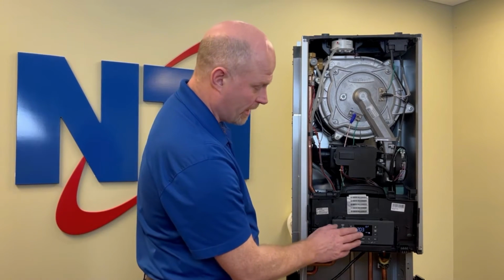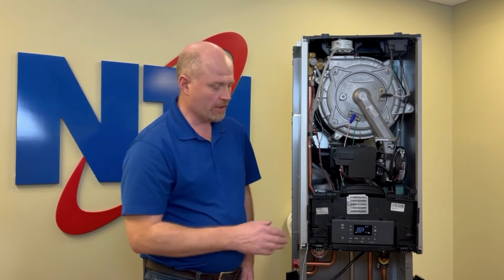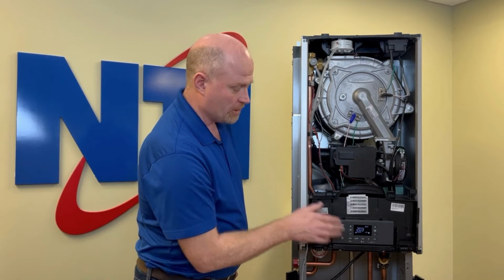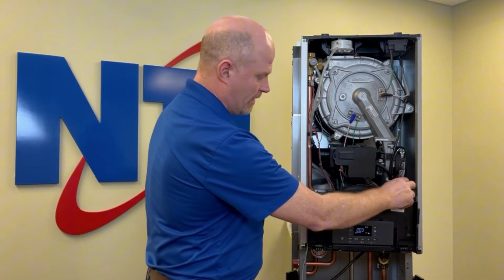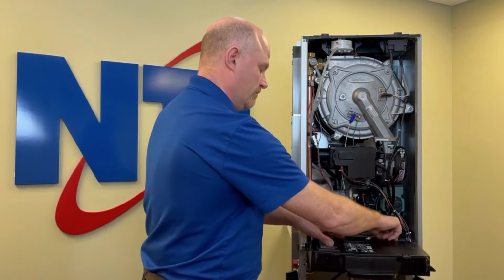My name is David Nicholson and today we're going to be troubleshooting error code 203. Error code 203 will come up because the boiler is looking for a tank temperature sensor but one is not connected.